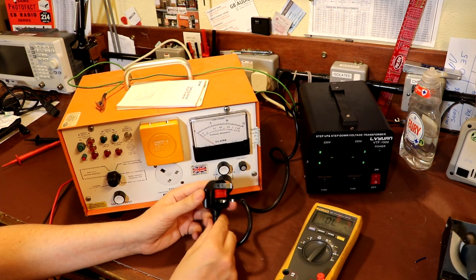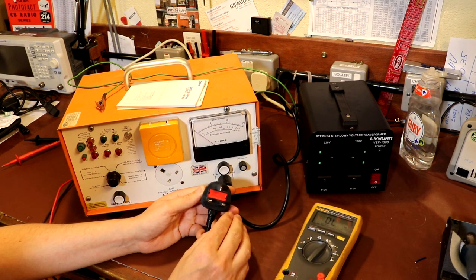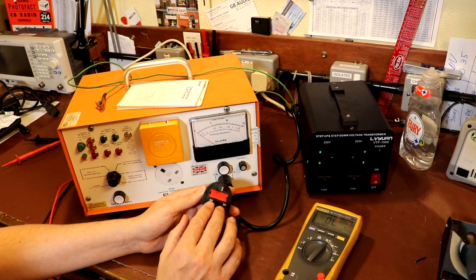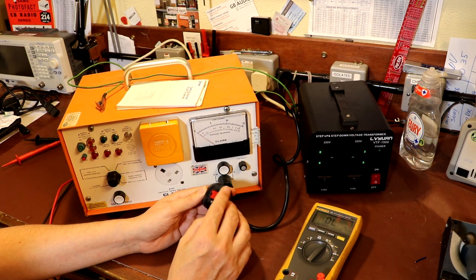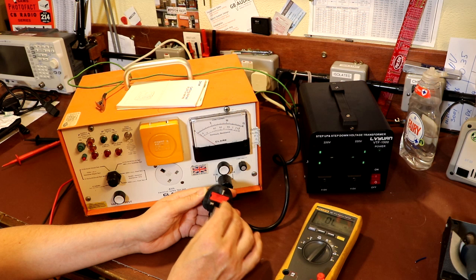Let's test it. So what we're going to be doing here is an insulation resistance test. We're going to supply a high voltage to both the live and neutral pins at the same time, and we're going to look for any leakage onto the earth pin. So that's an insulation test.